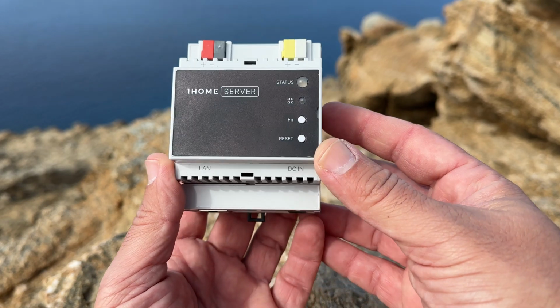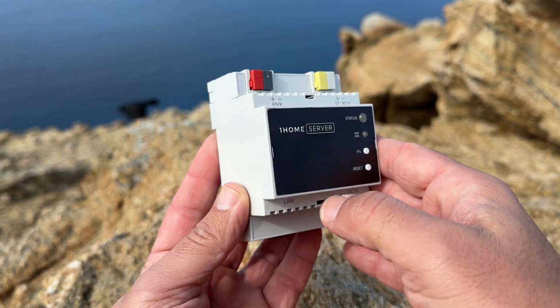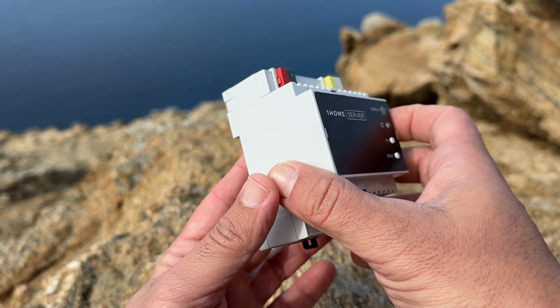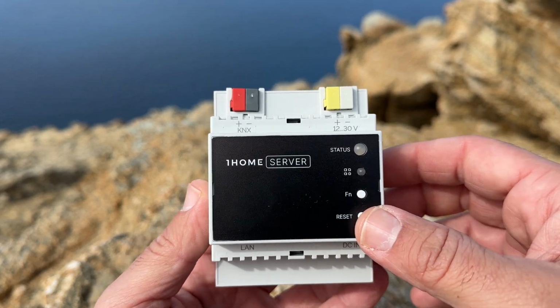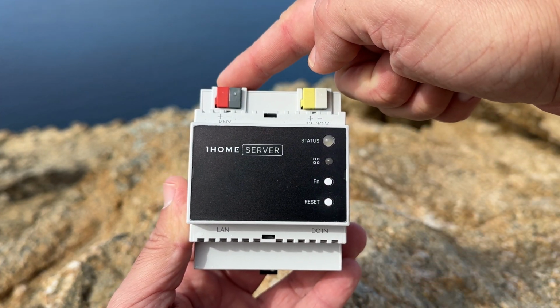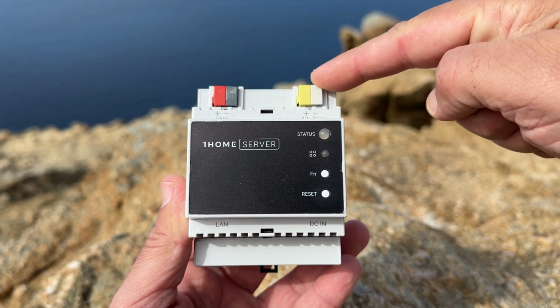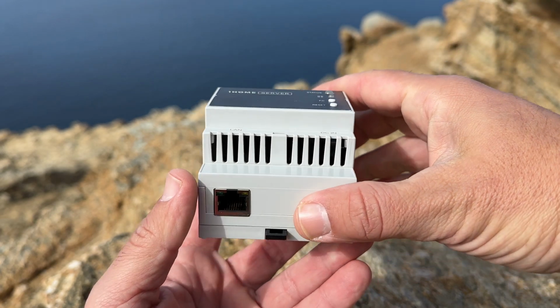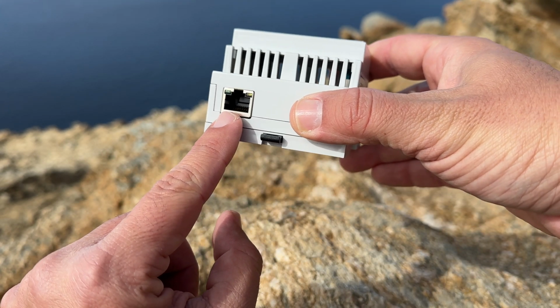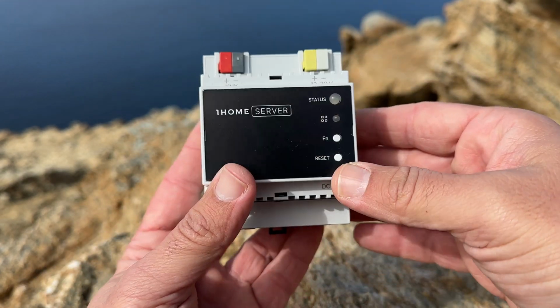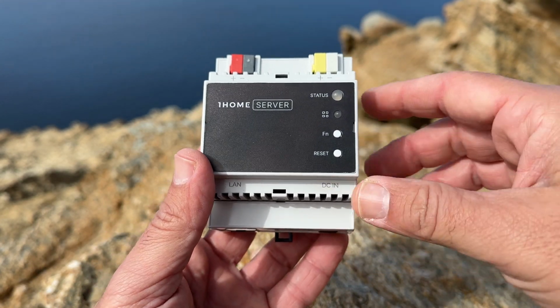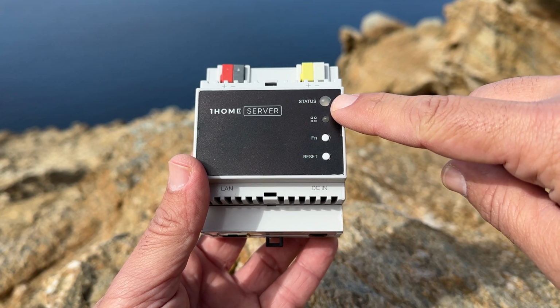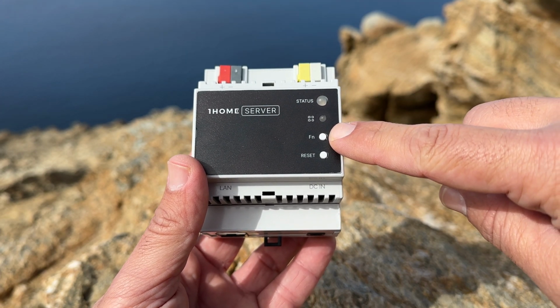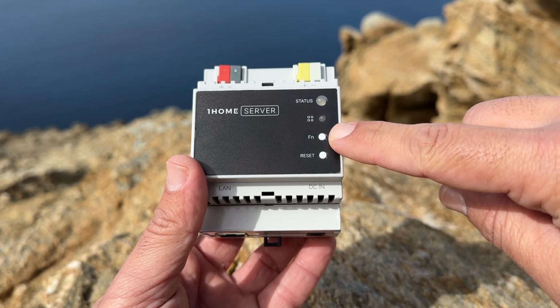This is the One Home server. The server is designed for DIN rail mounting and requires 4 DIN rail units. On the top side, you will find the red-black KNX bus connector and the yellow-white auxiliary connector. The One Home server requires a 12 to 30 volts DC power supply. On the bottom, there is an RJ45 LAN socket. On the front, you will find the status LED, a multifunctional red LED, a multifunctional button, currently not in use, and a reset button.